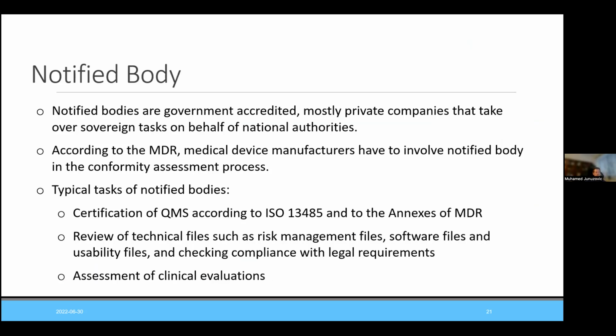And now one can ask who is going to check the technical documentation. So there are organizations called notified bodies. A notified body is usually a private company which is accredited by a government, and that company takes over tasks on behalf of national authorities. According to the medical device regulation, medical device manufacturers have to involve a notified body in the conformity assessment process. It is on the manufacturer to choose the notified body. There are no strict rules. So there are several companies in the area, and you can just choose one which fits your needs.